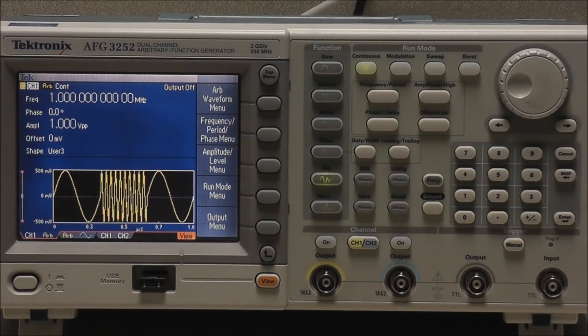A couple of usage tips when saving and recalling data: always save and recall waveform data first, and set up data second. Also you may want to verify the correct waveform is in use.